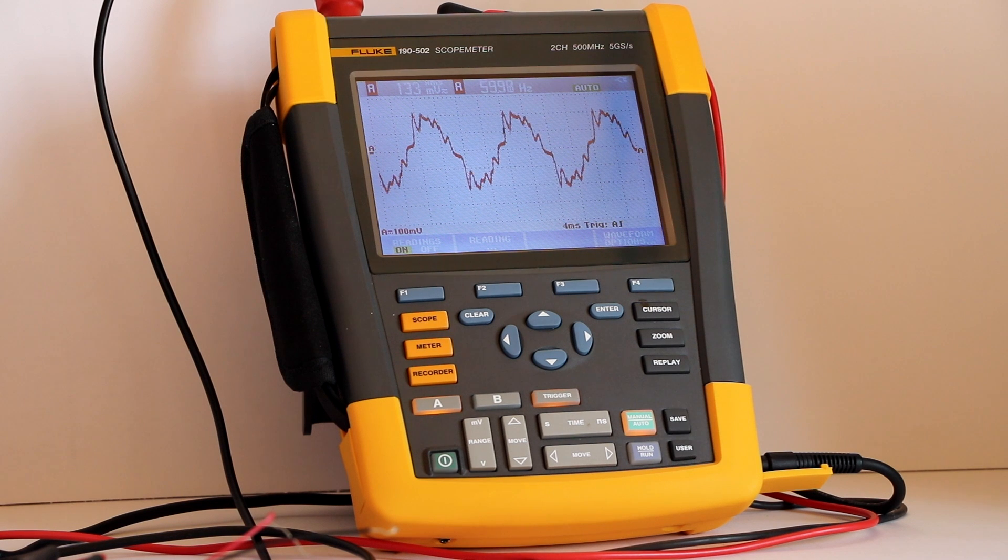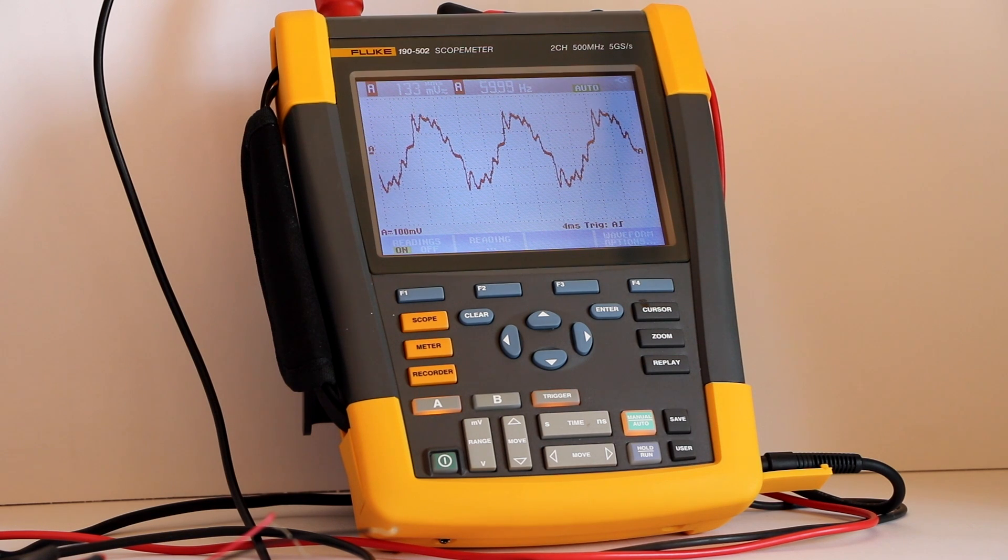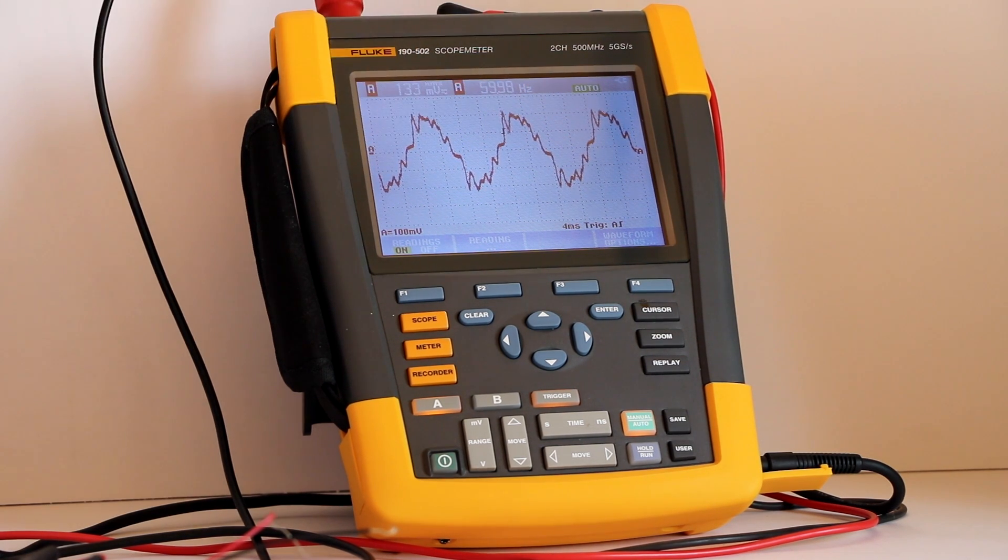First, an observation. The Fluke 190-502 scope meter is capable of operating off the AC power line with or without the internal battery in place. If the battery is installed, and if it is good, it will be charging whenever the AC power is connected. A small icon that looks like an AC power plug is in the upper right-hand corner of the display, and it indicates the instrument is receiving AC power. When the AC power is disconnected, if there is a good charged battery in place, the scope meter will continue to operate.